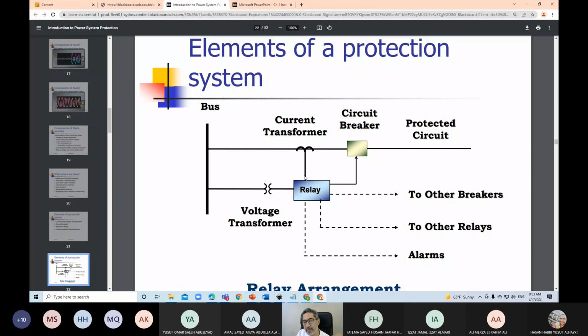Their purpose is to provide two things. They step down current and voltage to standard values suitable for the protective relays. And the second objective is to provide galvanic isolation, to isolate the high voltage system from the protection system. Okay, so they have two purposes.